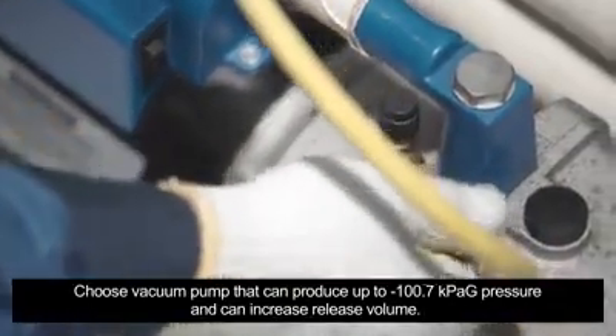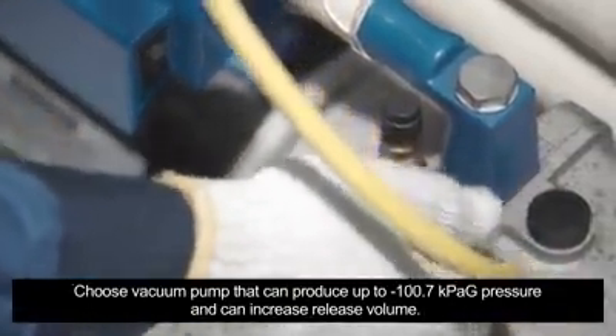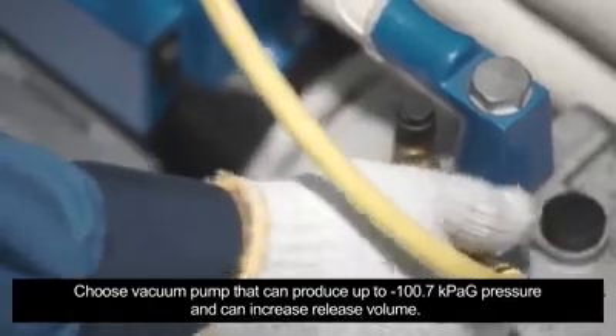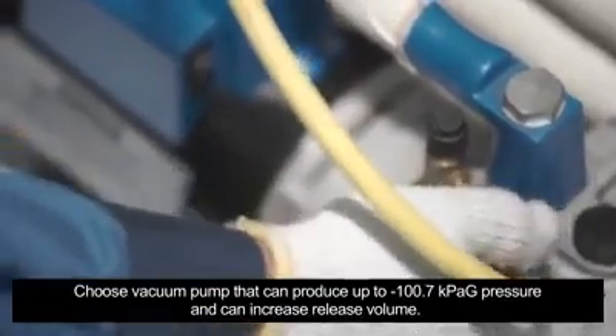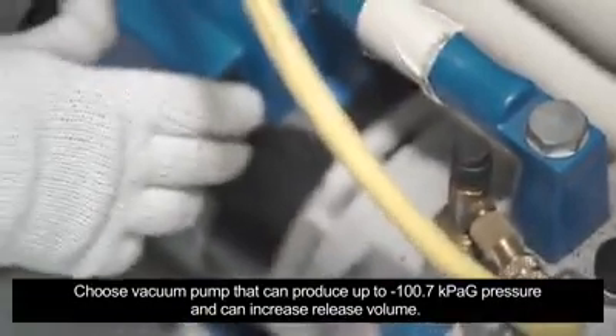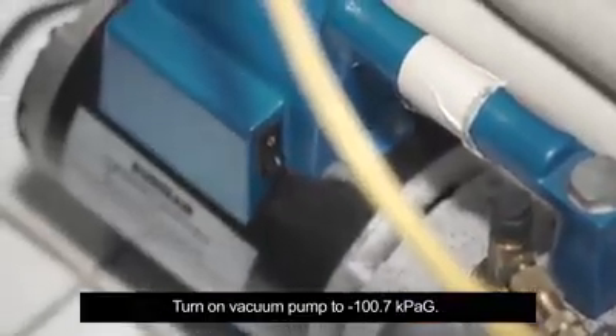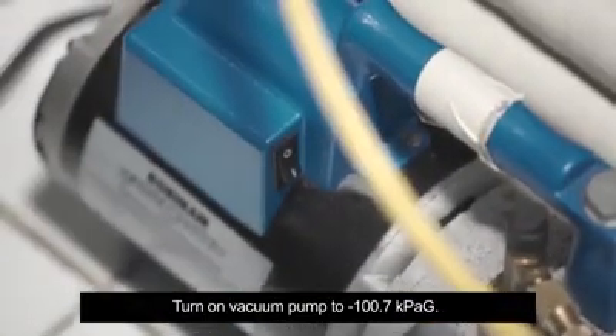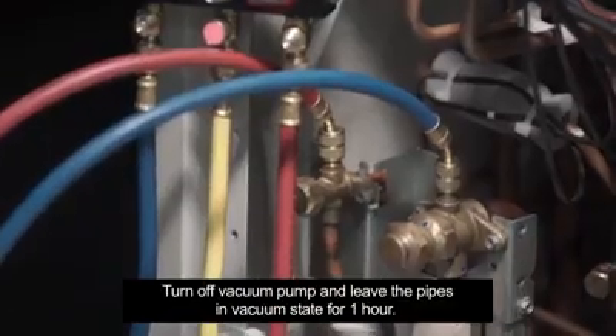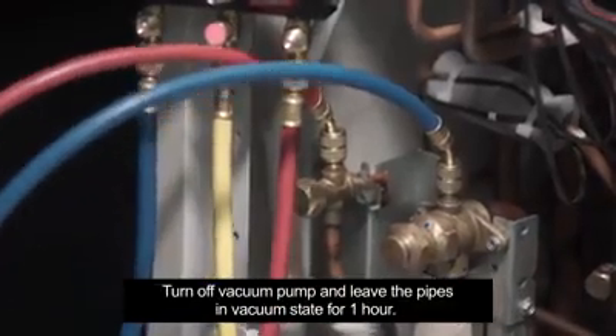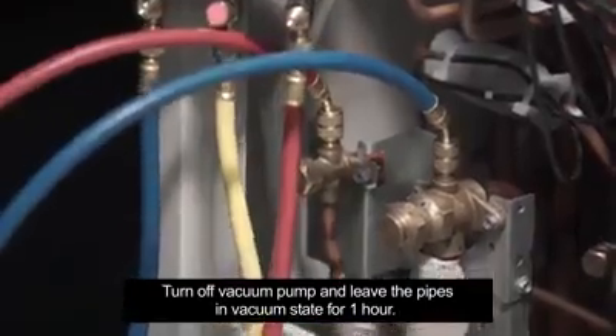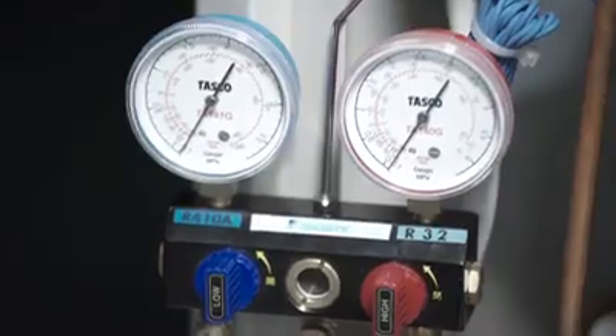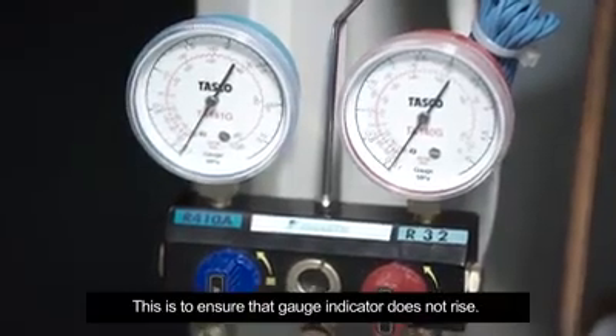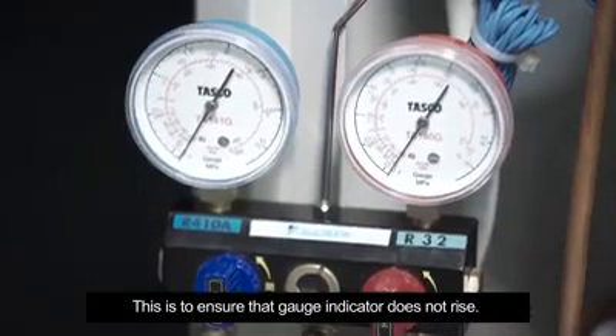Choose vacuum pump that can produce up to minus 100.7 kPa pressure and can increase release volume. Turn on vacuum pump to minus 100.7 kPa. Turn off vacuum pump and leave the pipes in vacuum state for 1 hour. This is to ensure that gauge indicator does not rise.